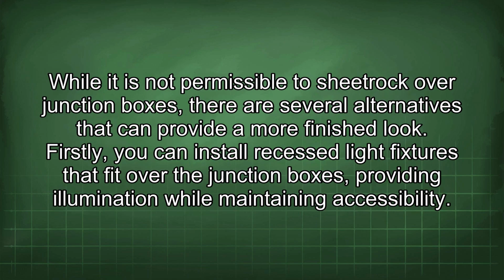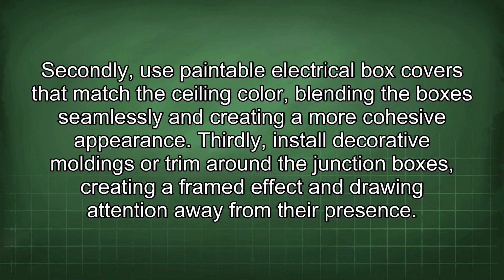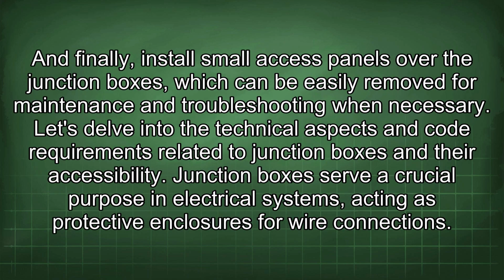While it is not permissible to sheetrock over junction boxes, there are several alternatives that can provide a more finished look. Firstly, you can install recessed light fixtures that fit over the junction boxes, providing illumination while maintaining accessibility. Secondly, use paintable electrical box covers that match the ceiling color, blending the boxes seamlessly and creating a more cohesive appearance. Thirdly, install decorative moldings or trim around the junction boxes, creating a framed effect and drawing attention away from their presence. And finally, install small access panels over the junction boxes, which can be easily removed for maintenance and troubleshooting when necessary.